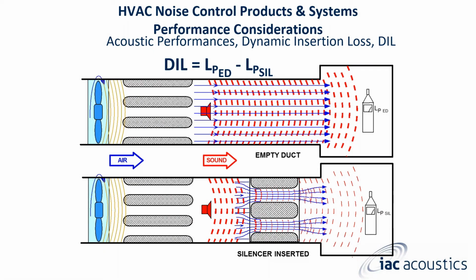Performance considerations for the acoustical performance: dynamic insertion loss, also known as DIL. You can see there at the top it has the cute little equation as well. But here, this is the type of loss that would be the difference between the sound power or intensity levels measured at the same point of the ductwork before and after the insertion of the silencer. And this is also shown in the forward flow here as well.